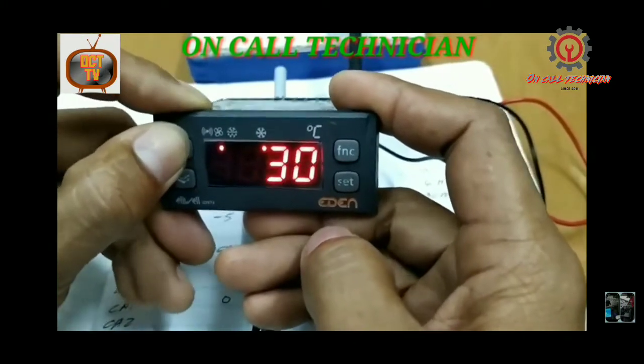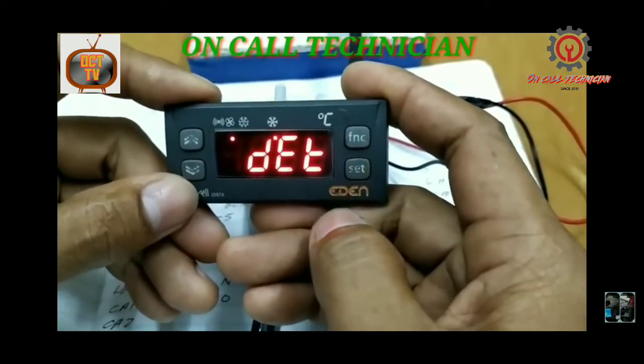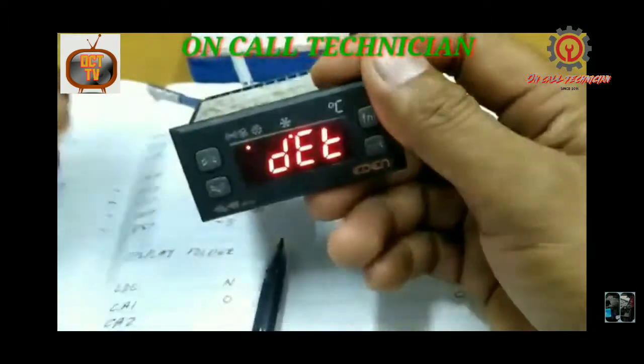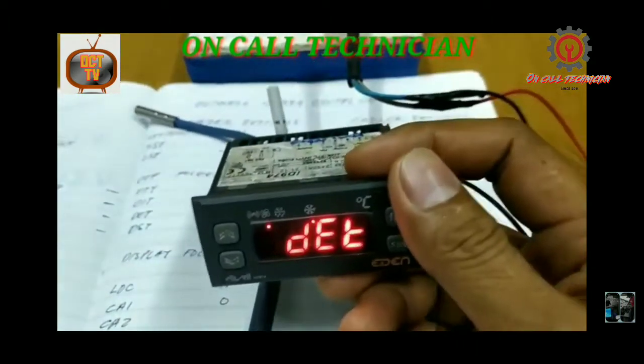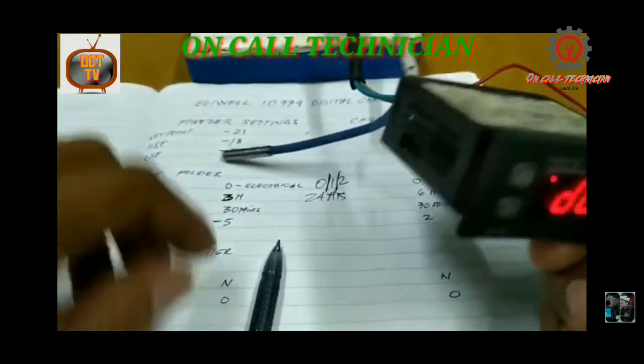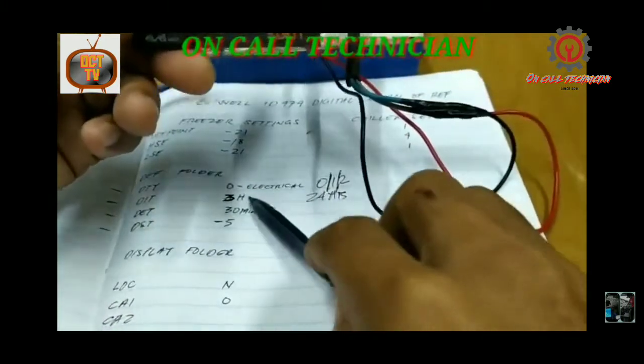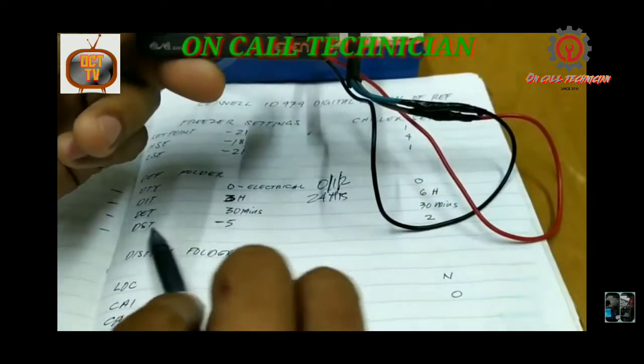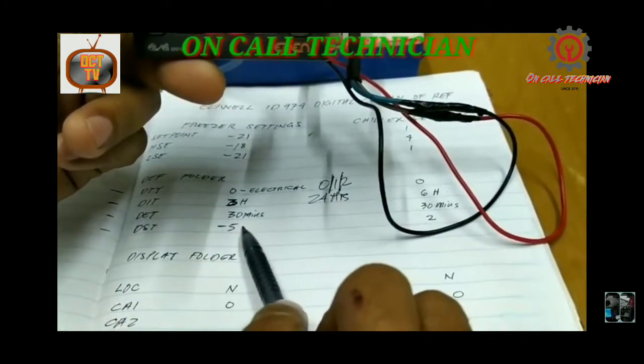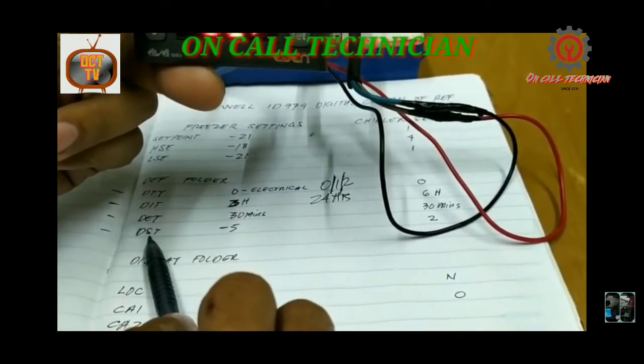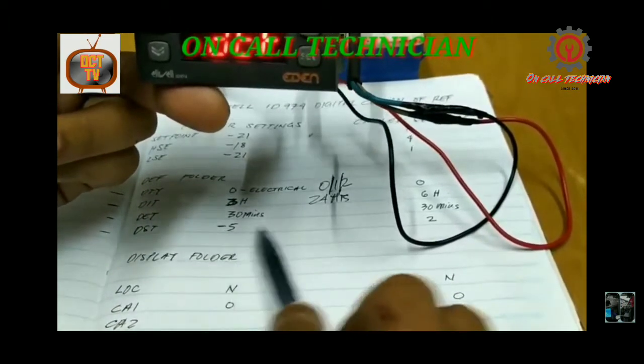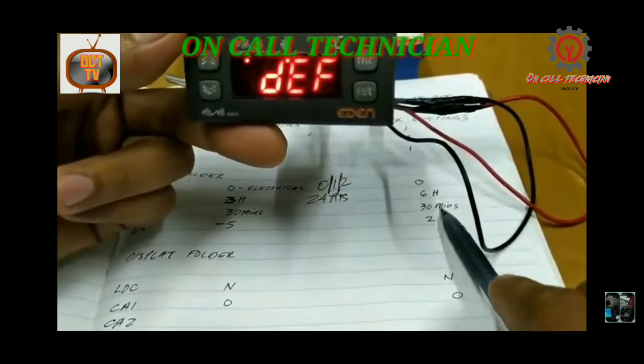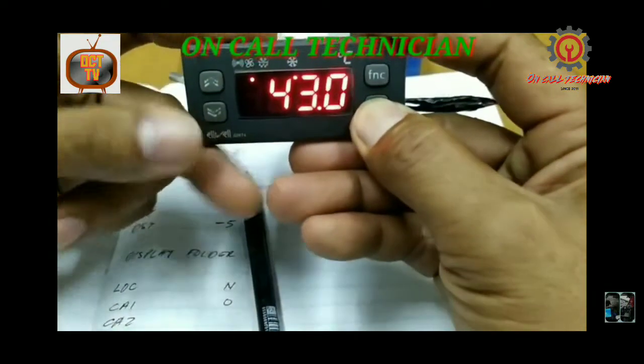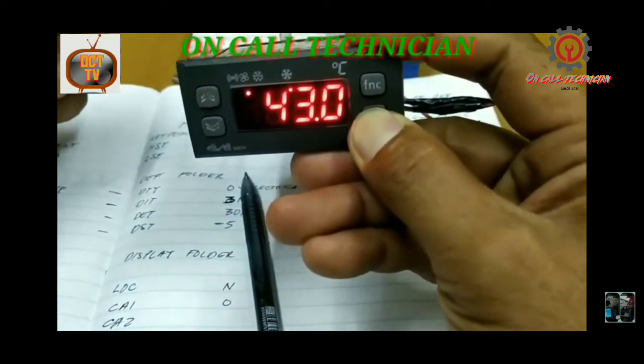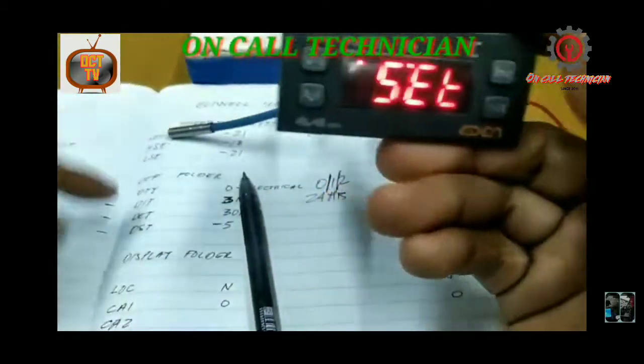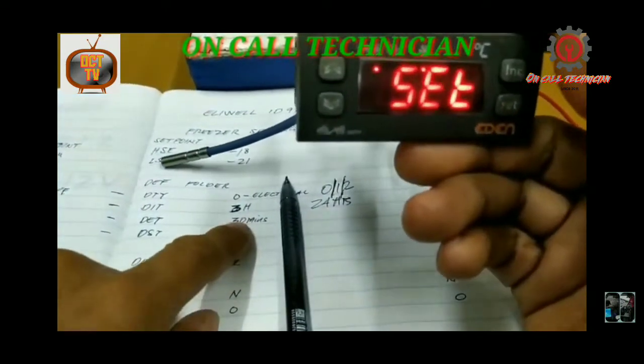Okay, guys, here it depends. If you want 30 minutes, it's okay. Okay, if you want 20 minutes, no problem. If you want 15 minutes, because the chiller is set to every 4 hours, no problem. But if you use that in every 8 hours, remember to adjust the DET to 30 minutes. Okay, and next, guys, is the DST. Okay, under the DST, it's -5 for the freezer. Okay, -5.